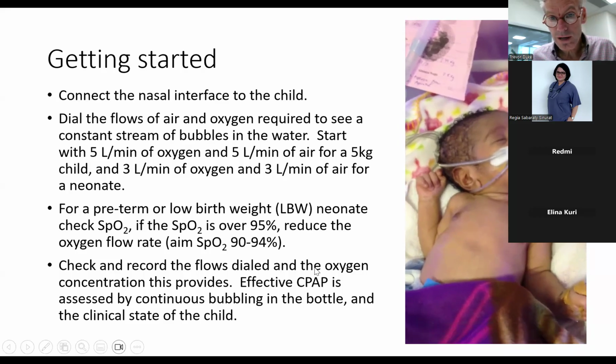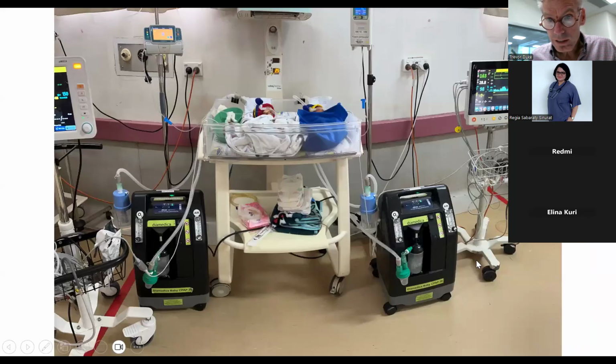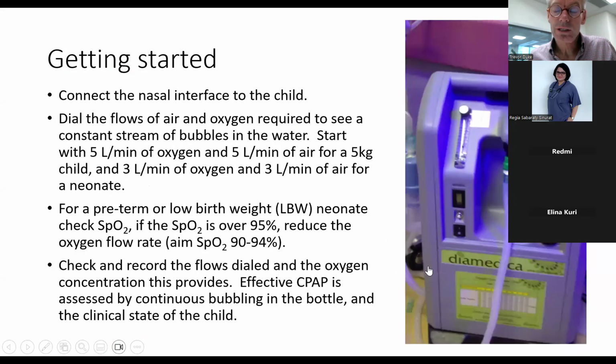The Diamedica machines also have, if I can just show you, a way that you can know the fraction of inspired oxygen you're delivering. The older machines have an algorithm that has, if you're giving, say, 5 of oxygen and 5 of air, then you're giving 57% oxygen. There's a table on the front of them, and we'll have to reproduce that in the new machines. If you're giving, say, 5 of air and only 1 of oxygen, you're probably giving about 25 to 30.